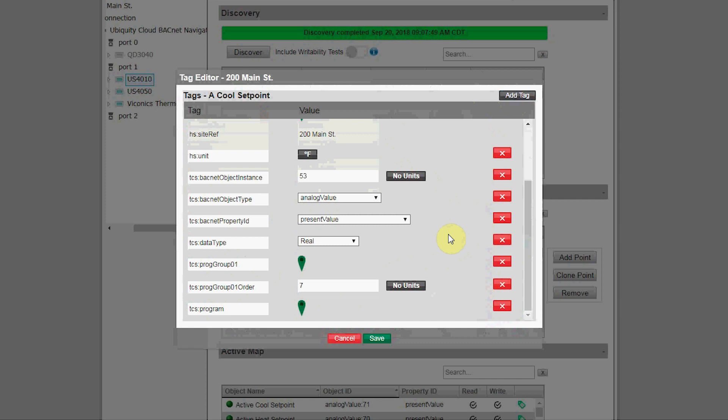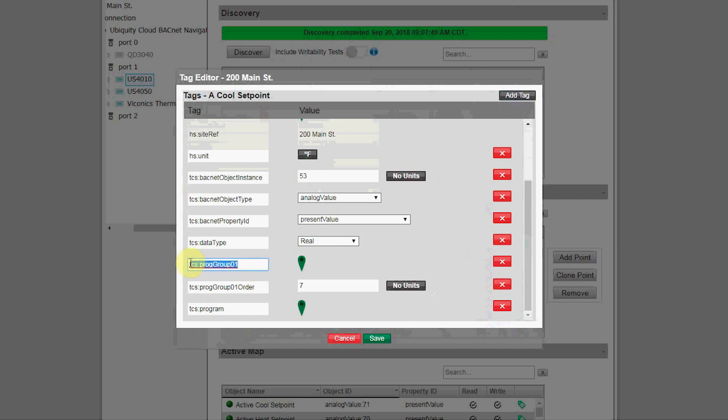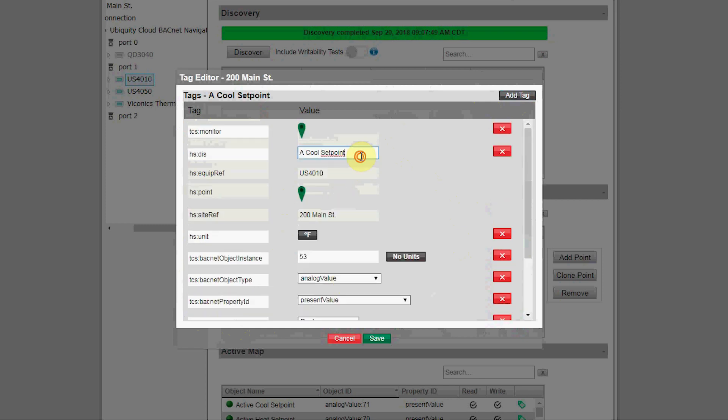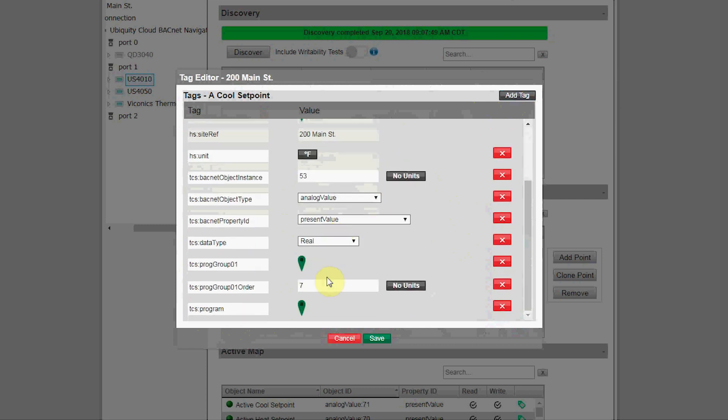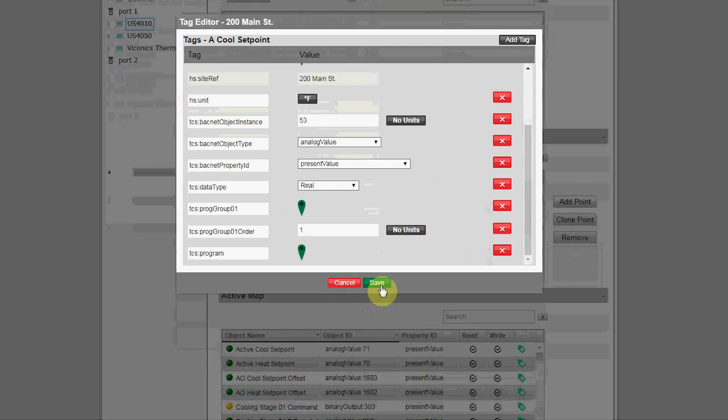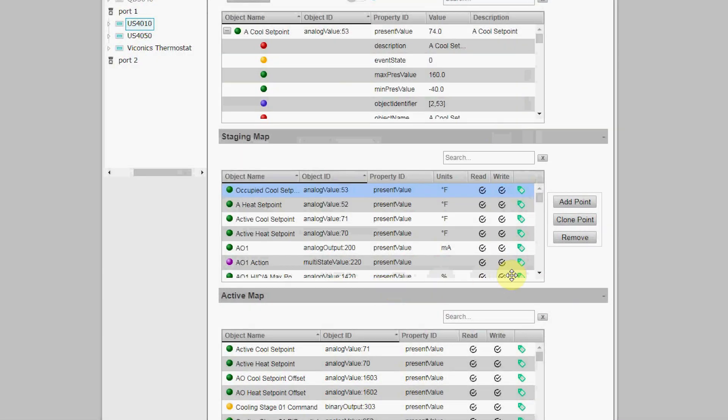This can also include tags to assign the object to groups within that page and positions within that group, as we showed previously on the monitoring and programming pages. For example, this A cool setpoint object, which has the BACnet object ID of Analog Value 53, is by default assigned to be programmed, then assigned to be in the first programming group and position 7 within that group. In this case, I'm going to rename this as Occupied Cool Setpoint, as I'm not going to use the B, C, and D setpoint objects, and then I change the position in the group to position number one.